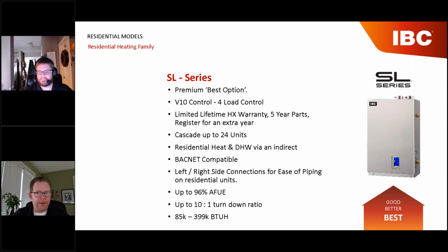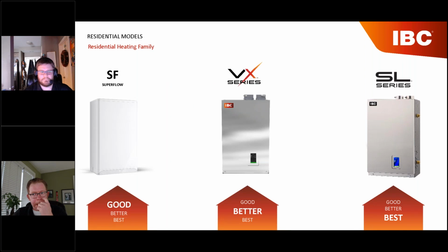It's up to 96% AFUE, with up to a 10 to 1 turndown ratio, and the residential units come in 85 to 399,000. That wraps up the good, better, best. I'll point out the SL units also come in much larger sizes, up to 850,000 BTUs now. We were the first in Ontario to put those units in, and Chris and I had lots of back and forth because we were pretty excited about it.